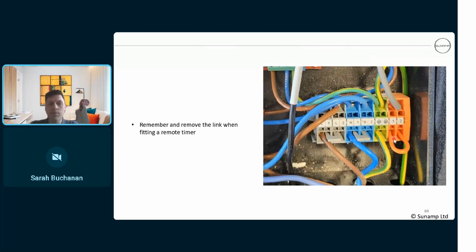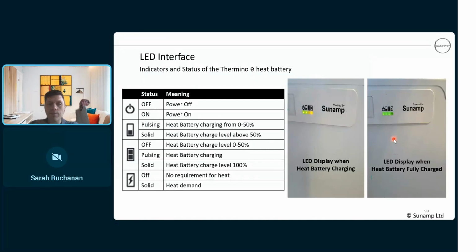if you're fitting a timer, remove the link. Believe it or not, we've had that fault from an installation out in the field. So just remove the link, because that's going to prioritize the timer timing over the overheat.